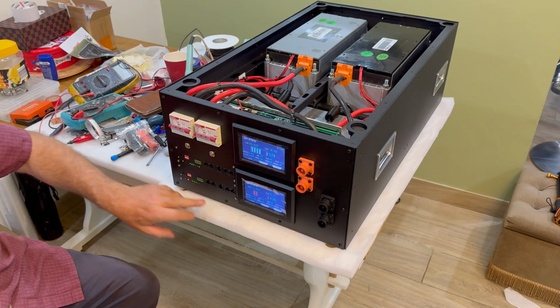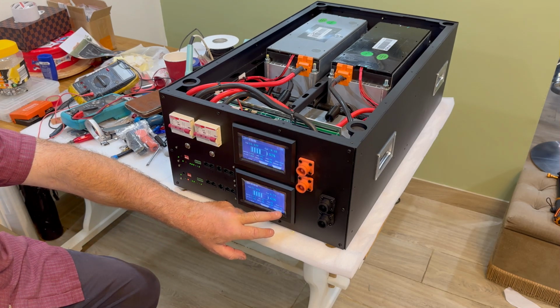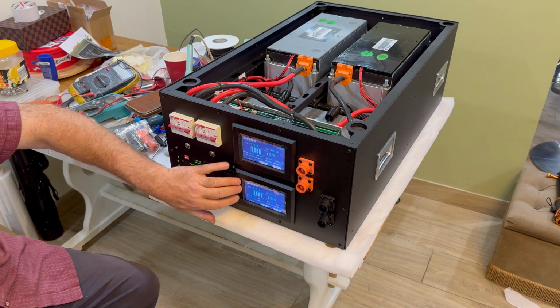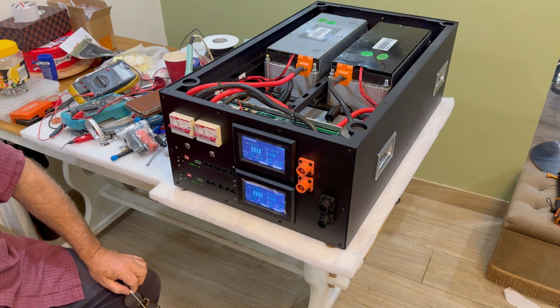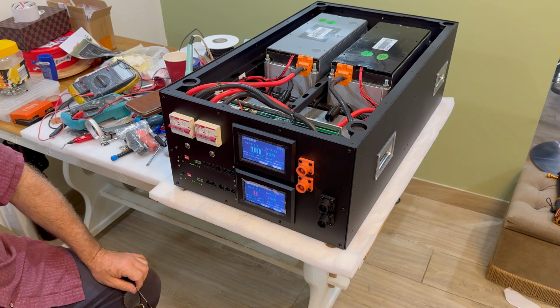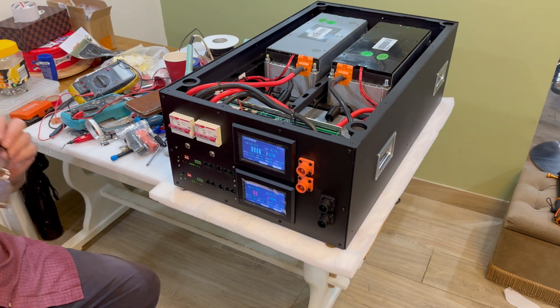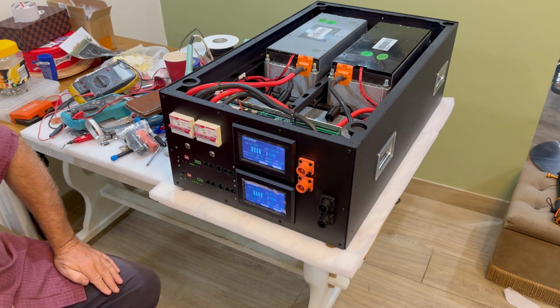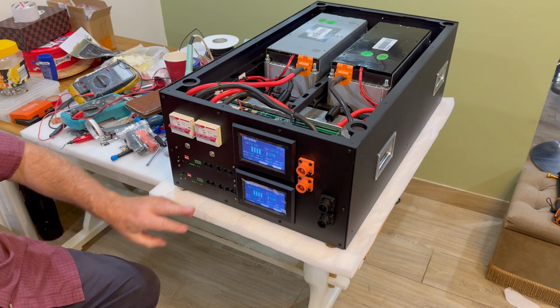You can see that's an alarm because it's saying I'm doing current protection on the charge, because the charge current was too high. I've set these to have a charge current of only about 35, maybe 40 amps maximum. That's configurable in the software - you can basically tell it how much current you want it to give, up to the limit of the BMS.